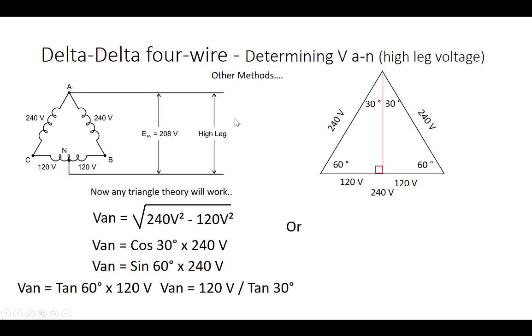There are a couple of methods of determining the high leg voltage. One method that can be used to solve the high leg voltage is to make a triangle of the voltages that we have on each phase. 240 on phase A to C, 240 on phase A to B, 240 on phase B to C with a center tap. And once we have that center tap, it does make a triangle for us as well, where the hypotenuse is 240 volts and the horizontal side is 120 volts. And if we're looking for the vertical side, that vertical side is the square root of the 240 volts squared minus 120 volts squared. So you can go through it this way to figure out what that high leg voltage is, or there's a much easier way that we often use.